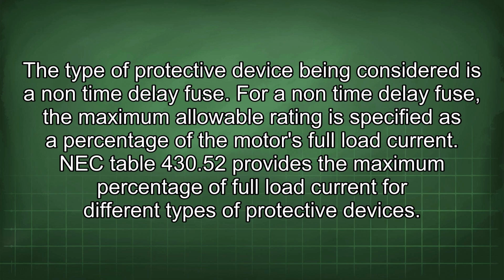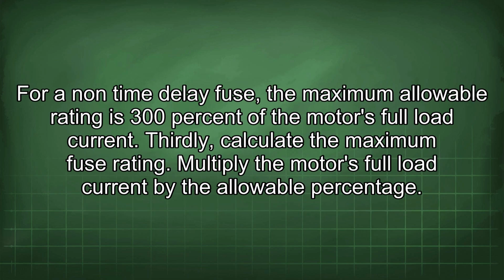For a non-time delay fuse, the maximum allowable rating is specified as a percentage of the motor's full load current. NEC Table 430.52 provides the maximum percentage of full load current for different types of protective devices. For a non-time delay fuse, the maximum allowable rating is 300% of the motor's full load current.